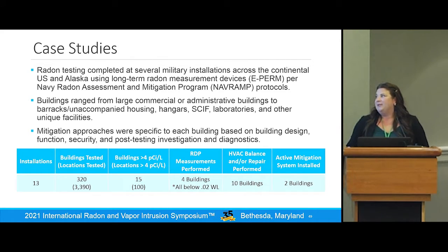We performed RDP measurements at 4 of the 15 elevated buildings. The exposure at all 4 was below the 0.02 working levels, with equilibrium factors all below 30%, some even below 15%. HVAC balance and/or repair was performed at 10 of the 15 buildings with elevated radon, and active mitigation systems were installed at 2 of those 15 buildings.